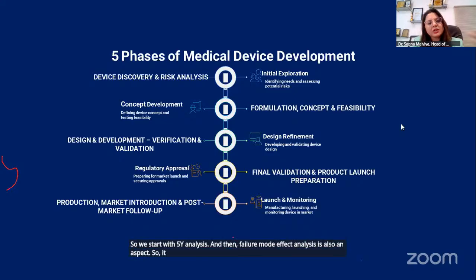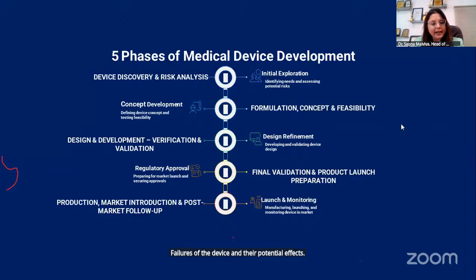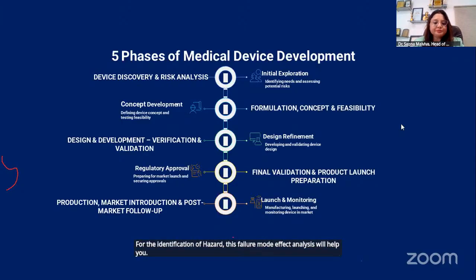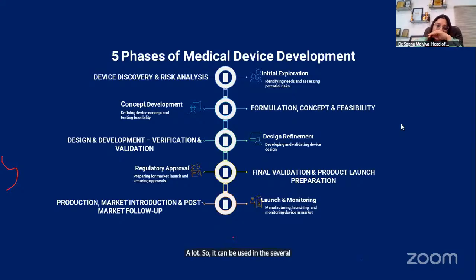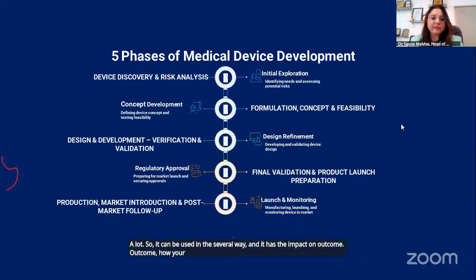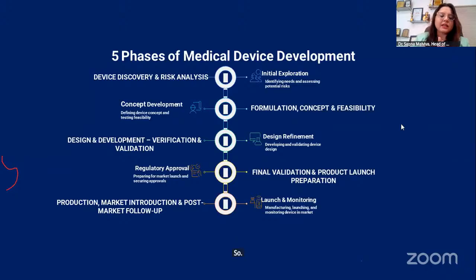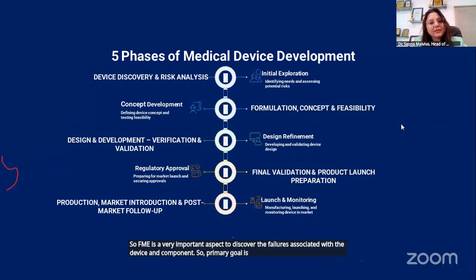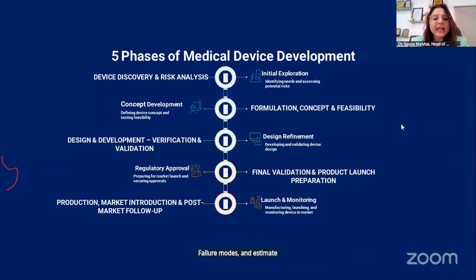So it is a structured approach where you can identify the potential failures of the device and their potential effects. So hazard identification as risk is an important factor. Risk analysis is very important for medical devices. So you need to identify the hazards. For the identification of hazard, this failure mode effect analysis will help you a lot. It can be used in several ways, and it has an impact on outcome, how your instrument which you have designed is going to work. So you need to identify, prioritize, and restrict the failure to the extent. FMEA is a very important aspect to discover the failures associated with the device and component. So the primary goal is to identify and assess the potential failure modes, estimate the severity, and mitigate the risk associated with the possible failure.